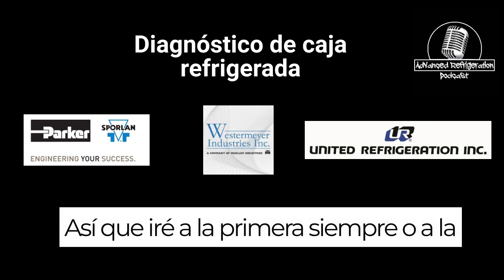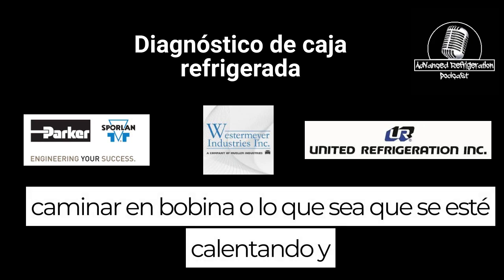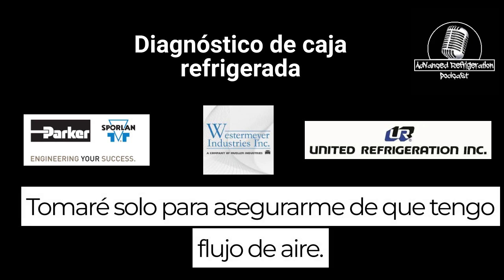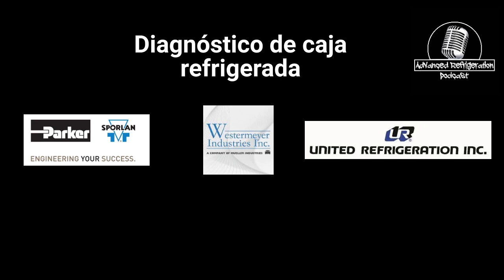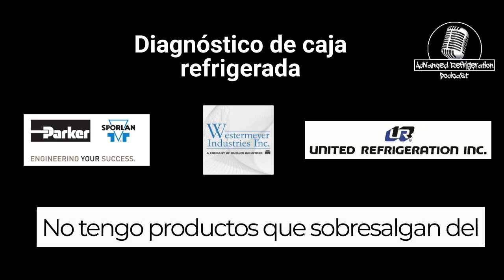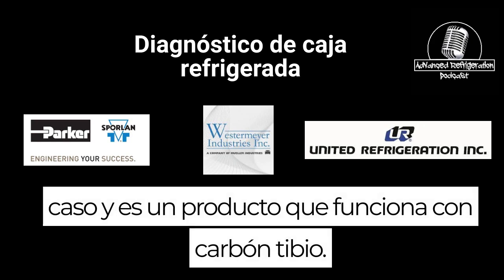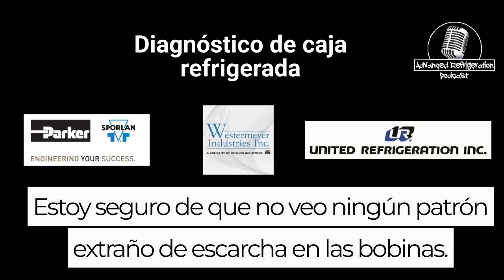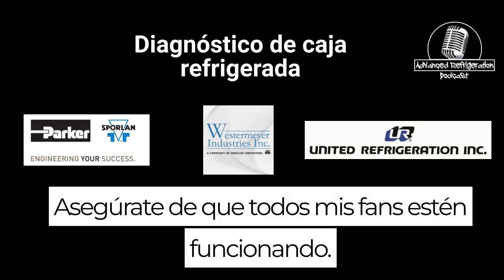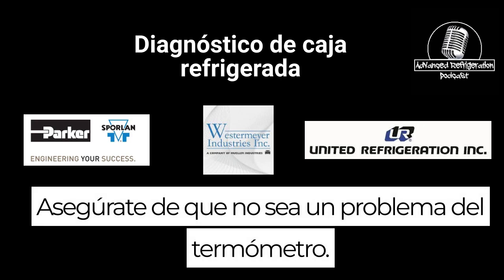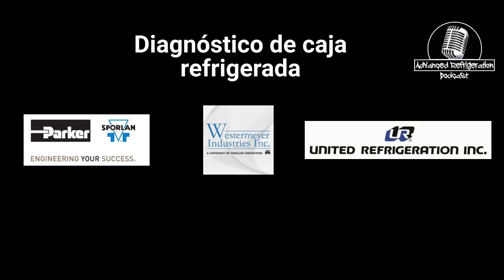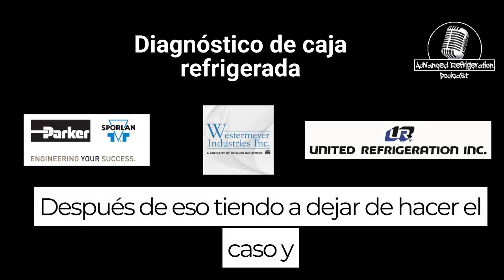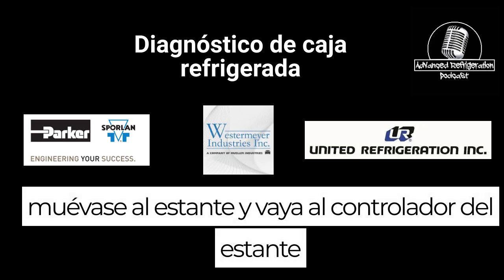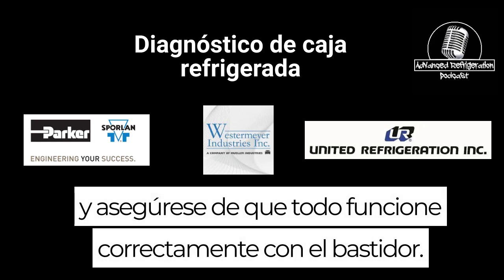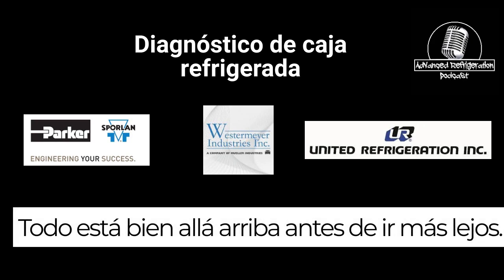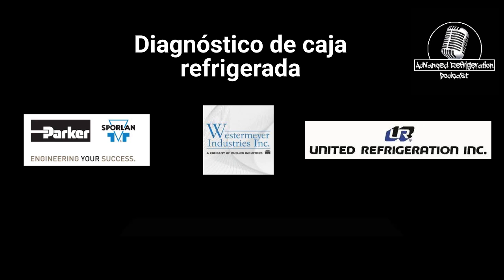So I'll go to the case first always, or the walk-in coil, or whatever's running warm, and take a look at it just to make sure I have airflow. I check that it's not iced up, that I don't have product sticking out of the case, and I check over the coil, make sure I don't see any weird frost patterns on the coils, make sure all my fans are working, and make sure it's not a thermometer issue, checking the case temperature real quick with my thermometer. After that, I move on to the rack and go to the rack controller and make sure everything is functioning properly with the rack. Everything's good up there before I go any farther and check superheats or pull strainers or do anything like that.